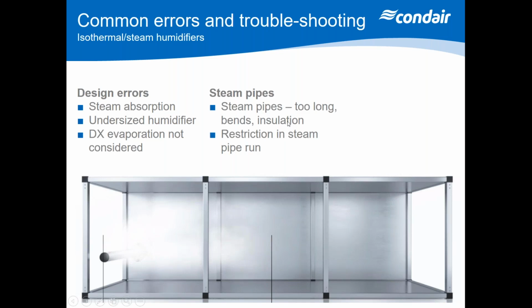Also, we see an awful lot where pipe runs are too long. Maximum efficiency for steam systems is 4 meters. If you go above that, then you're starting to lose more steam through condensate. Also, if you've got lots of bends, that's going to affect the output of the unit, and also restrictions like kinks will affect the outcome of the unit as well.